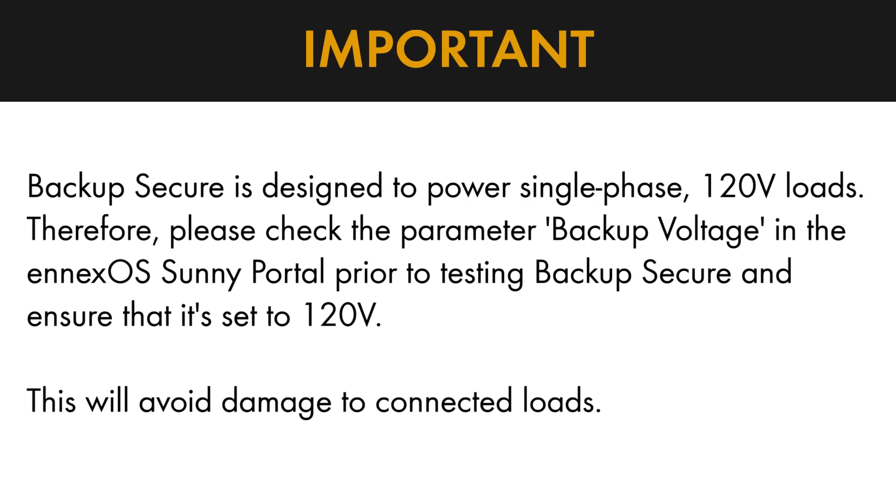Backup Secure is designed to power single-phase 120-volt loads. Therefore, please check the parameter Backup Voltage in the ennexOS Sunny Portal prior to testing Backup Secure and ensure that it's set to 120 volts. This will avoid damage to connected loads.